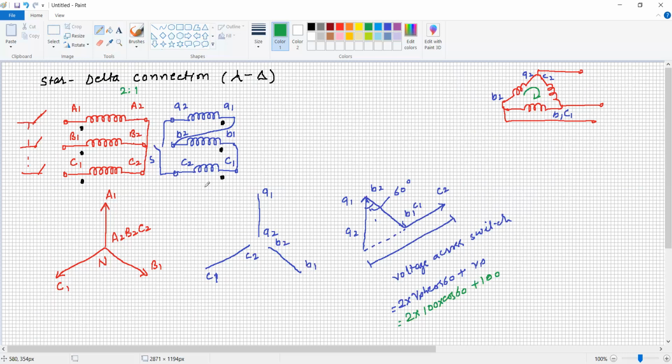So this is the wrong connection of delta, star to delta. If you are doing any three connections, those are connected in series, it will make delta. In the diagram, it will make delta, no doubt. But by neglecting this notation, a serious fault is going to occur in the secondary of the transformer, because it will circulate a large amount of current in the delta connection.